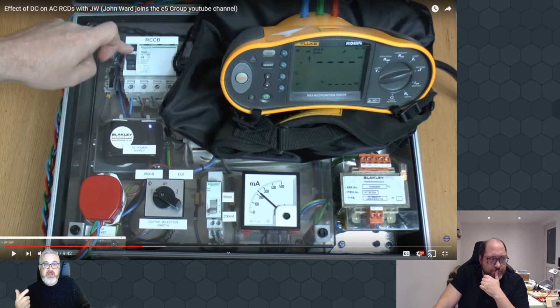If we go forward to the next one, this is the rig you'll have seen on many, many videos. I like to lend rigs out - this is a very simple and crude concoction. There's an RCD there, and in the video John is pushing the trip button, but because it's saturated, it's stunned, it's blinded, the circuit cannot generate a stable field because of DC saturation. It doesn't work. On the shunt trip, the little device next to the DC leakage, there's 250 milliamp being injected directly into the core to simulate what happens.